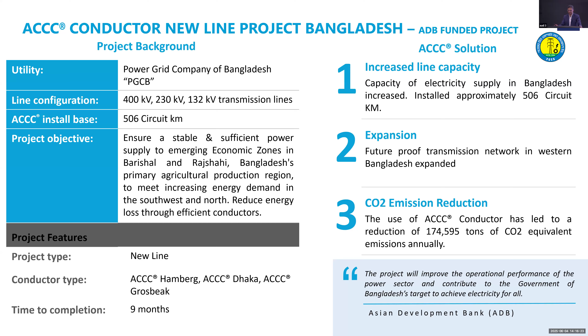Now, whenever it comes to planning for a new transmission line, the first consideration by any TSO, transmission system operator, is the first cost. And that's what they are always looking at, CapEx. What's the cost of the conductors? What's the cost of the transmission towers? That's what they're mainly looking at, right? Now, HTLS conductors carry more capacity in them. This is not being considered. They are always looking at dollar per meter, but HTLS can give you double the capacity. They should be looking at it as dollar per amp per meter or dollar per megawatt per meter, right? That is how we would like TSOs to start evaluating the selection of conductors, right?